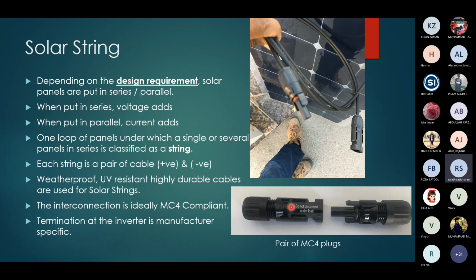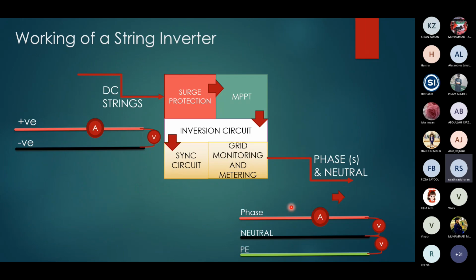If you disconnect it under load, it's going to give you a real health hazard because it can give you an arc flash. Ladies and gentlemen, I believe you have seen how a welding machine works, right? It works in the DC. And you can see that the moment that electrode is brought near a grounded metal conductor, you see how it creates an arc and melts the metal, right? So if you disconnect these connectors while it is under load or when the current is flowing through it, it is going to create such an arc. Now you can imagine the hazard behind it.